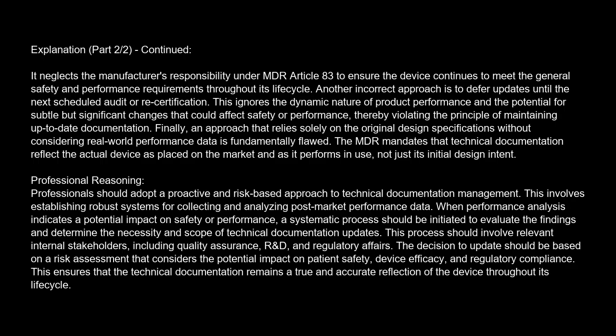This process should involve relevant internal stakeholders, including quality assurance, R&D, and regulatory affairs. The decision to update should be based on a risk assessment that considers the potential impact on patient safety, device efficacy, and regulatory compliance. This ensures that the technical documentation remains a true and accurate reflection of the device throughout its lifecycle.